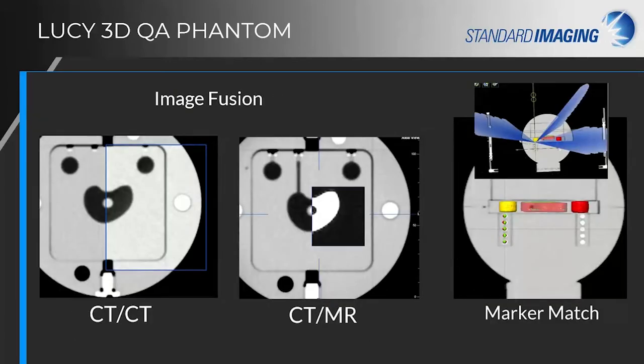Do your distance measurements. It's worth noting also that, as you see in the images here, we're using irregular volumes instead of just circles or spheres as the quickest way to really see any issues with your image fusion. After all, if you have a rotational issue, an arc on a circle is just an arc on a circle.